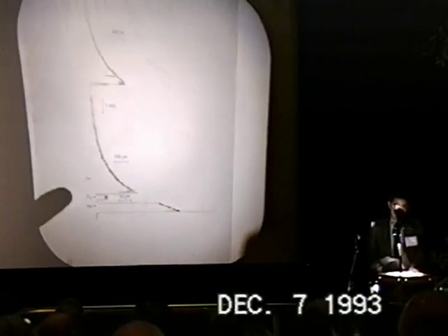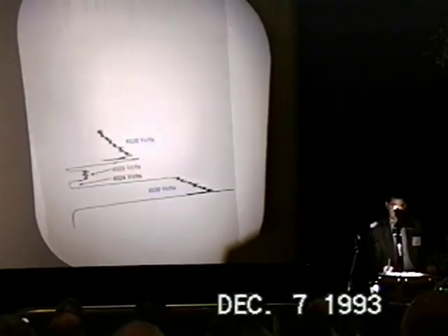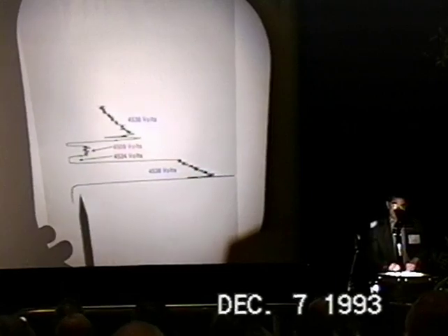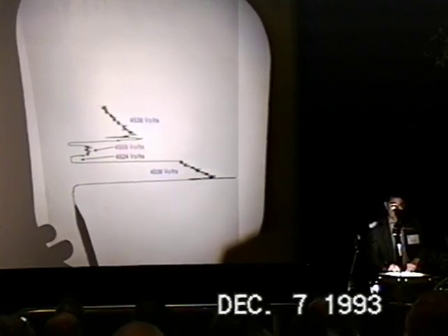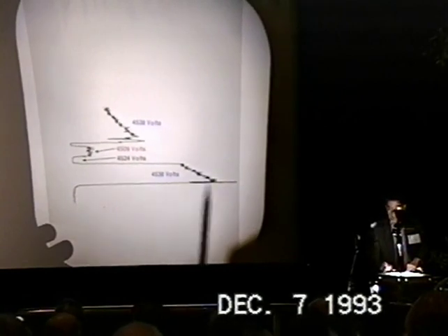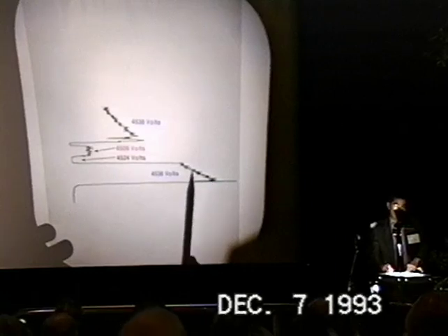But you may wonder how we are sure that we are on the helium mass. Well, we actually do a voltage scan, a helium peak versus voltage, so let's look at this larger portion. We are here before the helium signal goes up, before the opening of the closing valve. We are at this particular accelerating potential, so we are on the mass of the helium.